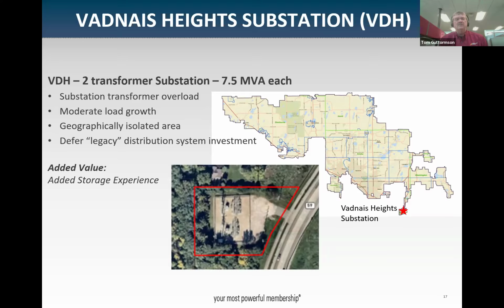So what we did, looking for a substation project - we thought, is there a substation out there with enough load that we might have to rebuild it, but not so bad that it needs a huge major project costing lots of money and giving more capacity than is really needed. Also, if we have substations around the edge of our service territory, if one goes out, it's challenging to serve that load from an alternate source.